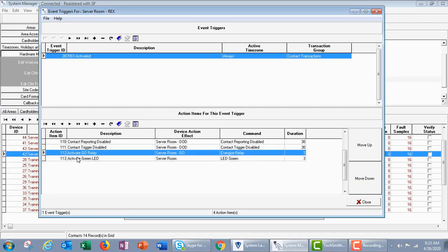If you were to remove them from this set of triggers, but you leave the request to exit on input 1, the request to exit will still energize the relay, because of degraded mode, because the reader interface is firmware programmed to energize the relay. So if you don't want the request to exit to energize the relay, you'll move the request to exit to input number 3, and then you'll delete these from our template.